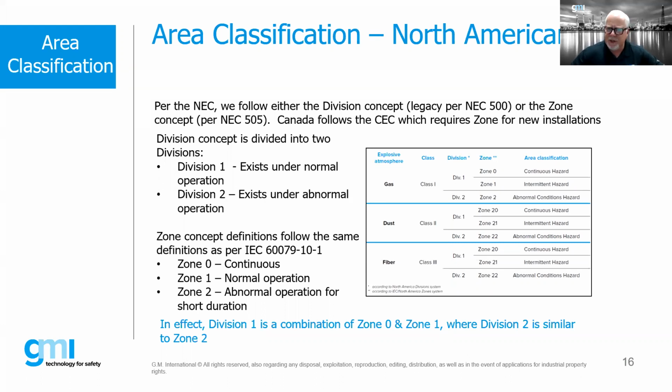And that additional step, by the way, is because within the US, the requirements are that products not only have to be certified for the hazardous location from an Ex perspective, but they also have to be certified against fire and shock hazards, which are not necessarily part of the requirements within the 60079 standards in the IEC world or in the EN world.